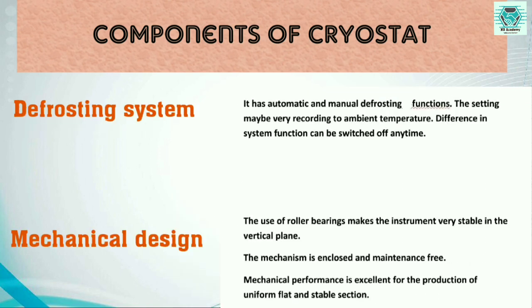The defrosting system has both automatic and manual defrosting functions. Defrosting time interval and manual defrosting time may be set; these settings can be varied according to the ambient temperature. The defrosting function and manual defrosting function can be switched off at any time.